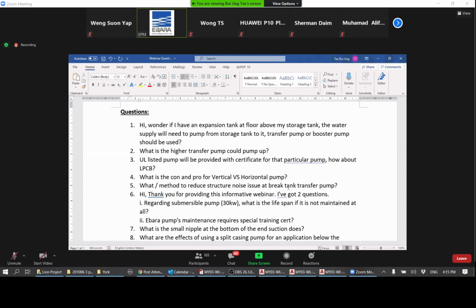So in such a case, we did not send our pump to the LPCB board simply because the demand is very small for LPC listed pumps in Malaysia. But if you are designing a fire system based on the LPC standard, which means that you're following the OH ordinary hazard standard, whether it's OH 1, 2 or 3, then our pumps comply with that standard.